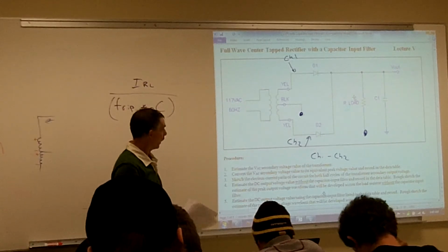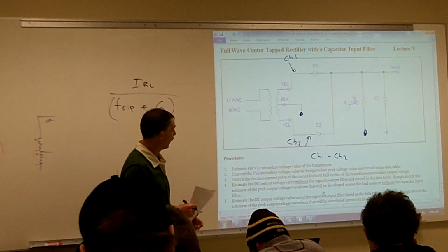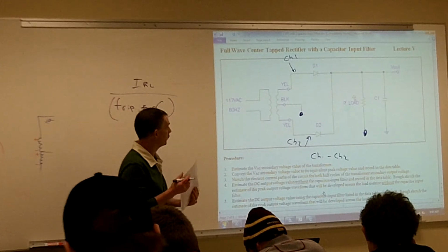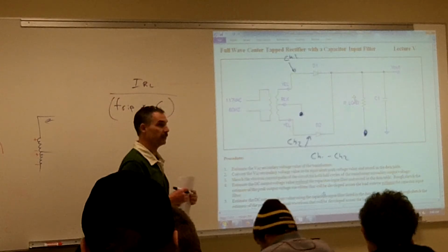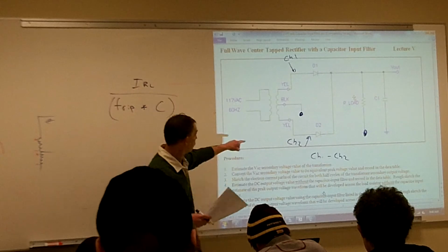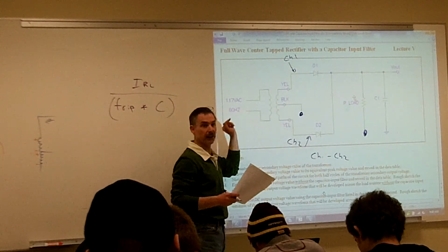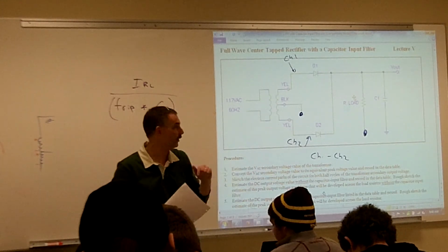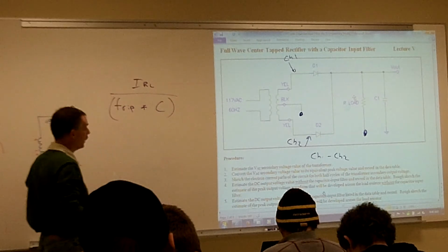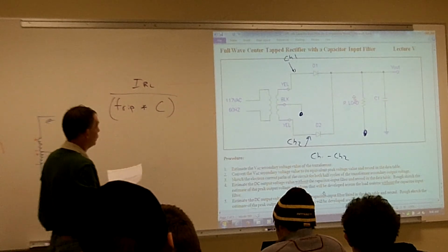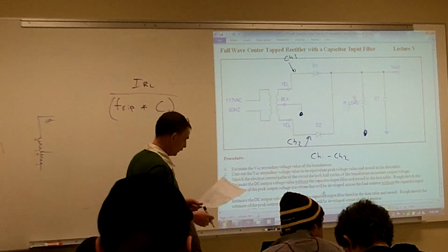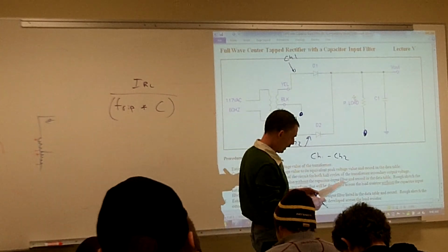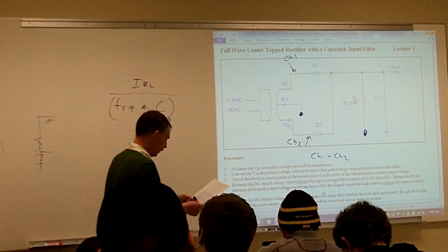Okay. So I have a few 100 milliamp fuses that go in your transformers. I'll be gladly to sell them to you. But if you end up floating that ground, you're going to end up burning out that 100 milliamp fuse in your transformer. So make sure you do a math calculation. Never float that ground. The minute you float that ground, you're going to short out your transformer. All right, well, that was the big one. That's the one that we really have to watch out for.